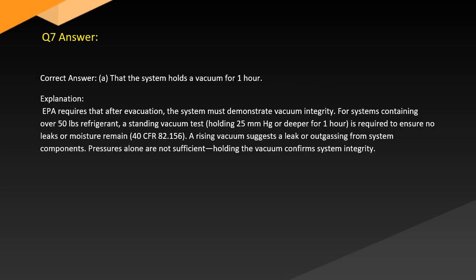Answer. Correct answer: A. That the system holds a vacuum for 1 hour. Explanation. EPA requires that after evacuation, the system must demonstrate vacuum integrity. For systems containing over 50 pounds of refrigerant, a standing vacuum test holding 25 mm Hg or deeper for 1 hour is required to ensure no leaks or moisture remain. 40 CFR 82.156. A rising vacuum suggests a leak or outgassing from system components. Pressure alone is not sufficient. Holding the vacuum confirms system integrity.